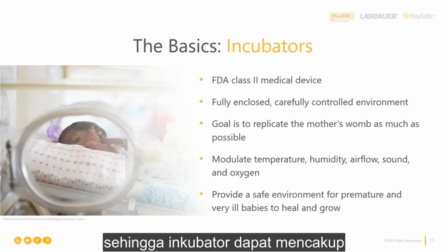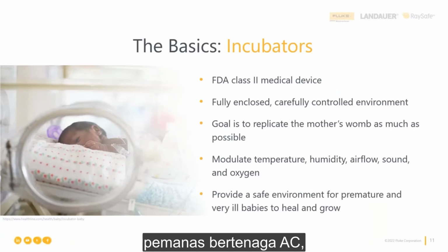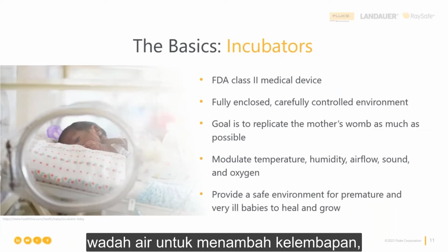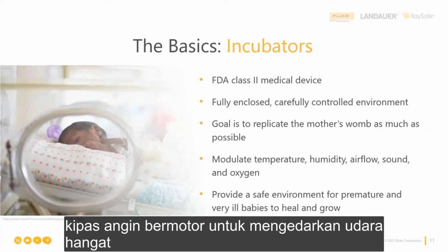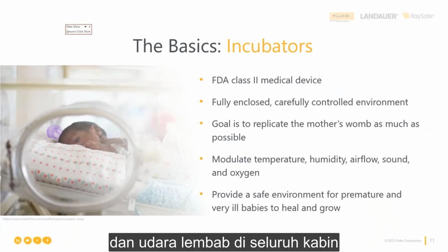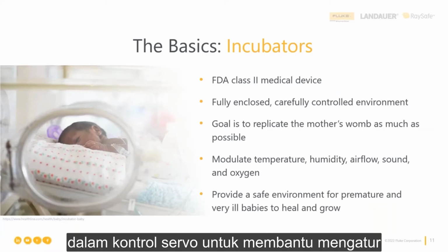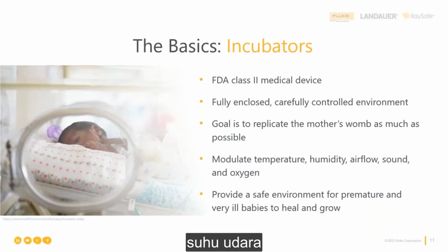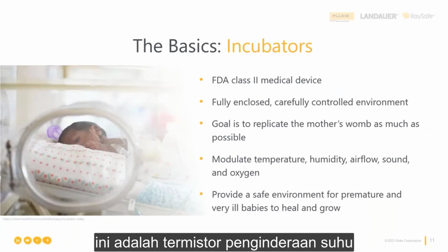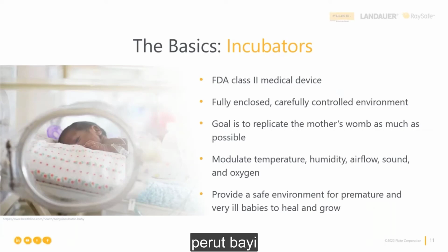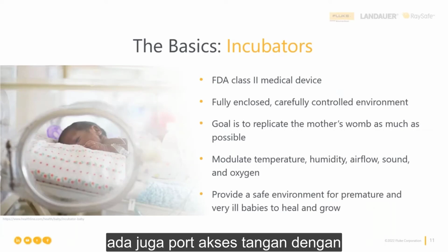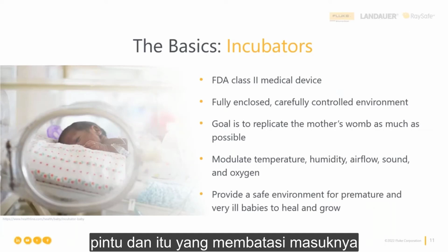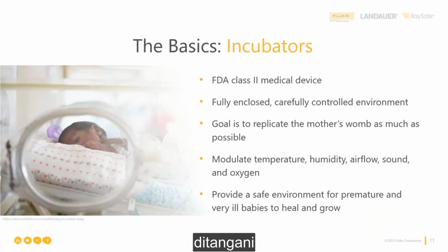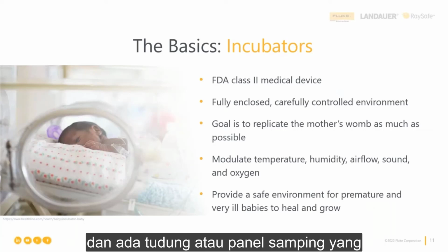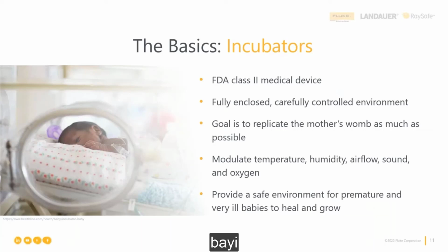So the incubator may include an AC-powered heater, a water container to add humidity, a motorized fan to circulate the warm and humid air throughout the cabin, a control valve through which oxygen may be added, and a servo control to help regulate air temperature. This is a temperature sensing thermistor that's usually taped to the infant's abdomen. There's also hand access ports with doors, and that limits the introduction of cooler air while the infant is being handled. And there's a hood or side panel that can be opened to gain greater access to the infant.